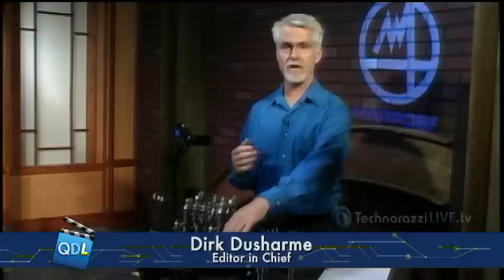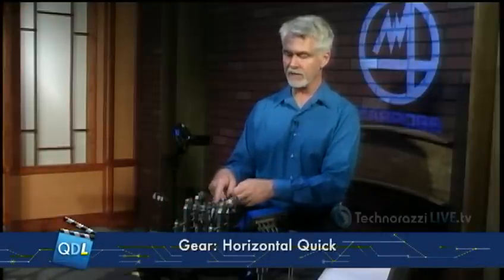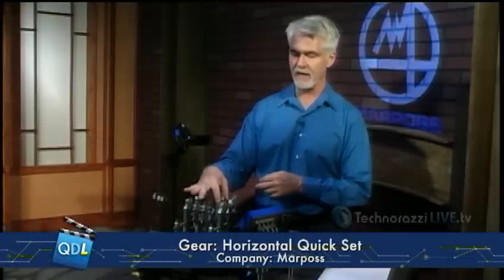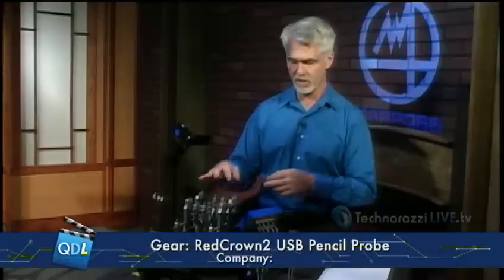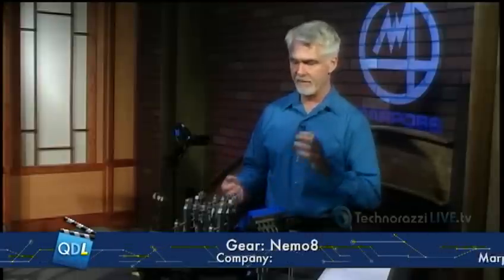Thanks Mike. We're going to look at a product from Marposs, and this is a manual gauging system intended for production gauging on the shop floor. We're going to look at three components: we've got the Marposs QuickSet, which is this whole big fixture right here; we're going to take a look at the Red Crown 2 probes, which are the LVDT probes that will be in the fixture; and we're going to look at the Nemo 8.